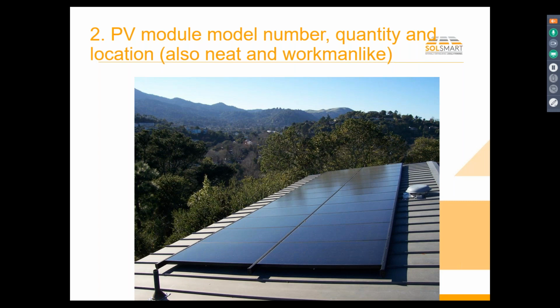Calculations could be wrong. I'm the field inspector, my job is to make sure it matches what was approved. Somebody sat down and approved a set of plans, and I'm out there to see if they did exactly that. They specified wire sizes, the modules, the inverter. Is that what's there, and is it put together right?